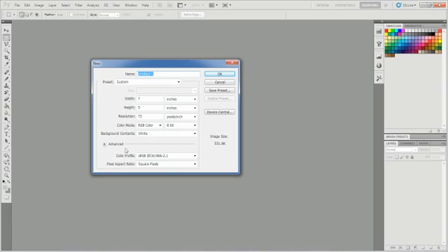One note of caution is that depending on your BAS, you typically should not resize the symbols that we provide. The reason is that the static PNGs match the size of the animated GIFs which you load into your BAS. And depending on your BAS, you might not be able to resize the animation to fit the background image. So be sure to pick a size from the start that will be able to fit the majority of the systems on one graphic. I'm going to use a pre-made template which is 1073 by 827 pixels as a background.